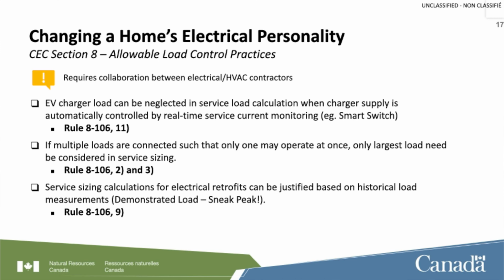So if you've got 3 or 4 things on one of these load miser monitoring devices, and it taps out at 40 amps, which is pretty much your type 2 EV charger - if it hits 41 amps, somebody tries to use the EV charger with the electric dryer, everything shuts down. You still only have to put on your application the largest load, which would be your EV charger. So the splitting and sharing can actually bring down your requirement.